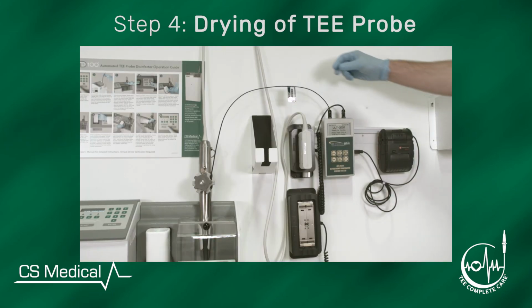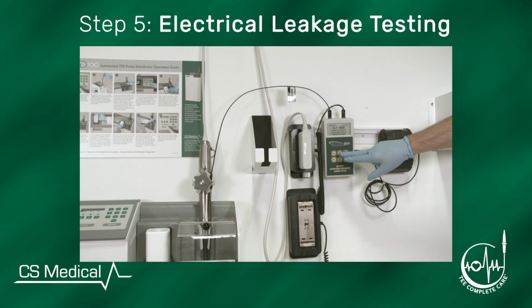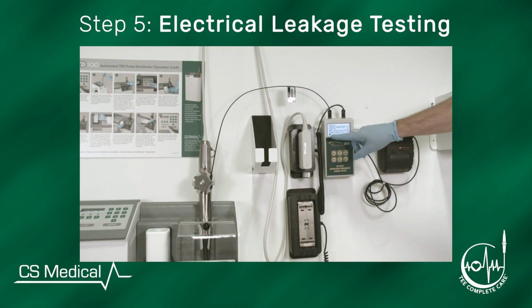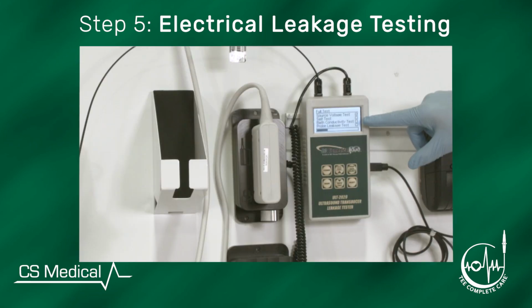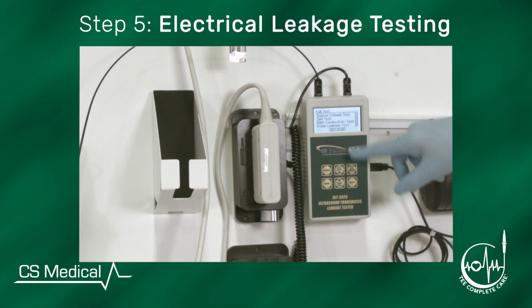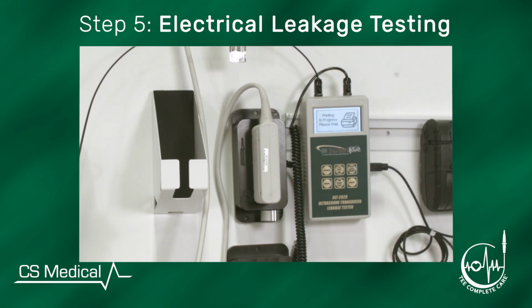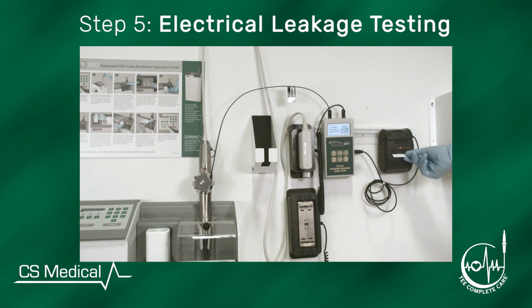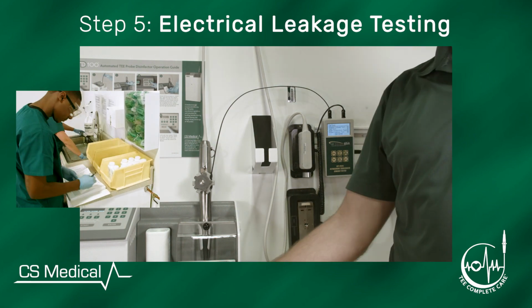Step 5. Per the IAC recommendation, all TEE probes should be electrically leakage tested between patient uses. CS Medical offers the ability to conduct electrical leakage testing inside the disinfectant reservoir, thus minimizing the need for additional containers of liquid to accomplish this requirement. By conducting the leakage test inside the automated disinfector, you minimize probe handling that could result in damage to the transducer. The HLD tracker can be used to document the successful completion of this requirement.